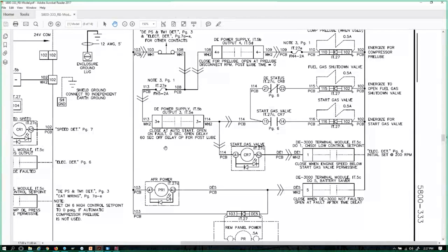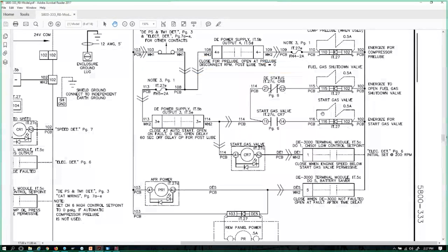And it should really say, for post lube option, open delay 60 seconds or 60-second off delay. So what we're saying is if we revert back to the software, if we want this valve to open back up on a fault and allow pressure to be available for a post lube event for a period of 60 seconds, we can jump completely back. I'm going to save the changes I made and then jump back.